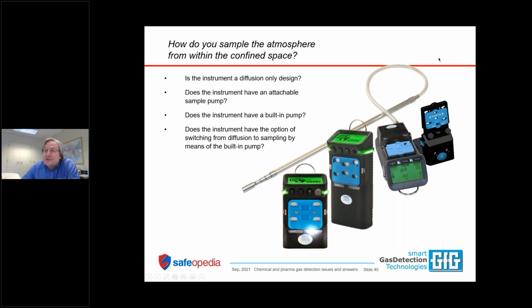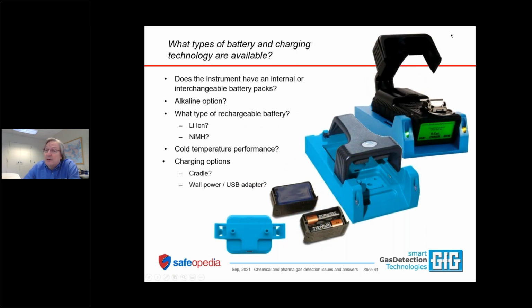Make sure that you address how you're going to use the instrument for confined space measurement where you need to have a pump. You can have a diffusion instrument. You can have an attachable pump that draws power from its own battery pack. You can have an internal pump that draws power from the instrument battery. And in this case, it has a slide switch that when you have the pump off, it operates in diffusion mode. When you have the pump on, you're pulling a sample through the hose and probe assembly. So you have a few different ways to go.